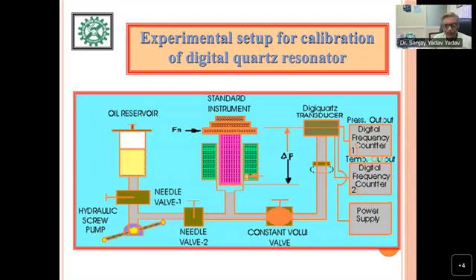All this you have to install. And then for the reference plane, generally, if there is no marking on the transducer, it is a convention to take the central part of the transducer as the reference plane, and the bottom of the piston at the reference standard. So this way you can calibrate the transducer. And transducer calibration can be made in two ways. One method is just putting a mass on the standard and seeing the measurement reading on the transducer. Another method is you adjust the mass on the dead weight tester according to the fixed value of the transducer.